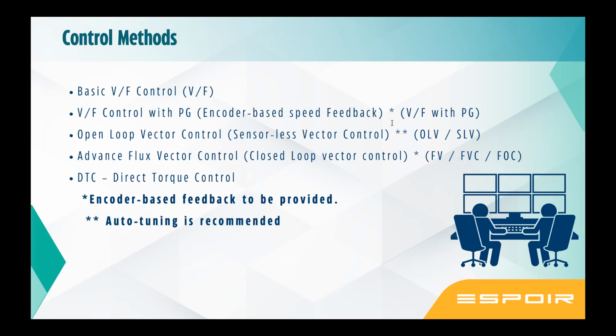The V by F ratio should be maintained constant. It means that if you change the frequency, say you want to reduce the speed to 50%, you reduce the frequency from 50 Hertz to 25 Hertz. Now, if you do not change the voltage, the voltage is 400 but the frequency is 25 Hertz. What happens? The flux is going to be enormous, and it can create an overheating issue. So you need to reduce the voltage also in the same ratio as the frequency. If you reduce the frequency by 50%, you also reduce the voltage by 50%, which is 200 volts on a 400 volt system. So 200 volts and the frequency is 25. The ratio is 8. This is the V by F ratio. This ratio we need to maintain constantly.